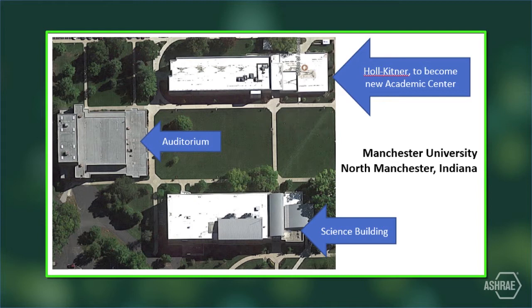All three buildings need reheat for summer humidity control, but it was not available at HK or the auditorium because the campus steam system was off from April through September. Chilled water mains connect all three buildings, but the campus loop was short of capacity.